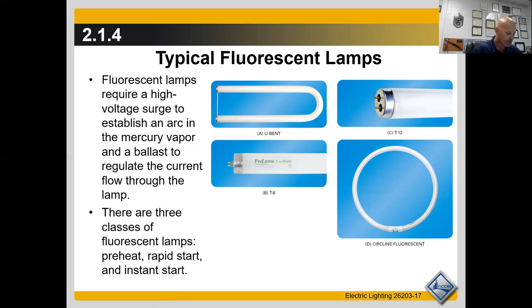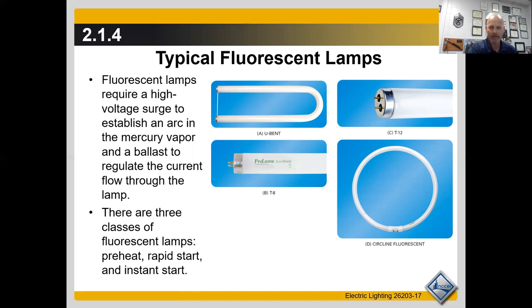Fluorescent lamps have two electrical requirements: a high voltage surge is needed to establish an arc in the mercury vapor to start the lamp, and once started, the gas offers decreasing resistance, so current must be regulated to match that drop. Unlike an incandescent with a tungsten filament, this gas doesn't have the same resistance, so it doesn't require as much energy to maintain the light. The ballast regulates voltage going in and out of the tube. Once the initial arc is created, the tube continues to work as long as voltage is applied.